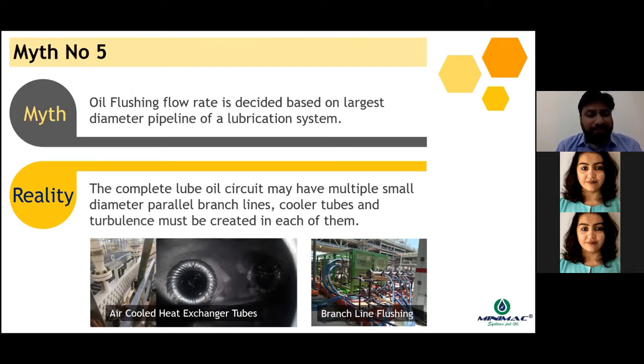And when the oil is fed into these heat exchangers, it would get divided into the multiple loops or the multiple tubes. Thereby the entire flow rate would be diminished to less than a 10th of the requirement of each of these tubes. So how are we ensuring turbulent flow inside each of these tubes? Unless we do a calculation for performing flushing on these heat exchanger tubes, we must not follow the advice of handling the port size and, based on that, calculating the flushing flow rate.